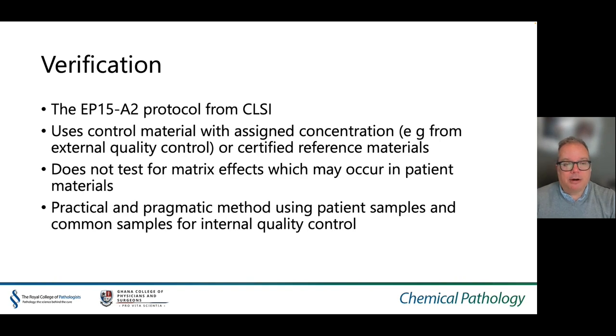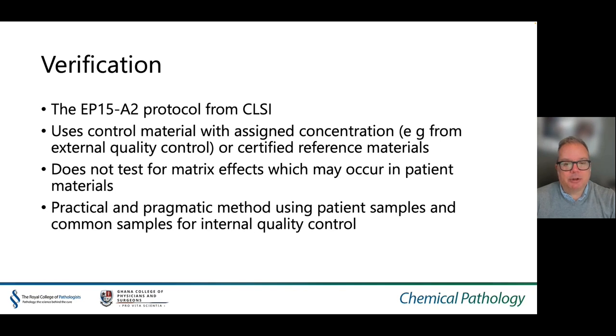There are recognised standards available for verification, and the EP15-A2 document from CLSI is a very good starting point for any verification exercise. It uses control material with assigned concentration, for example from external quality control or certified reference materials. It does not, however, test for matrix effect which may occur in patient materials, but it is a practical and pragmatic method using patient samples and common samples for internal quality control.